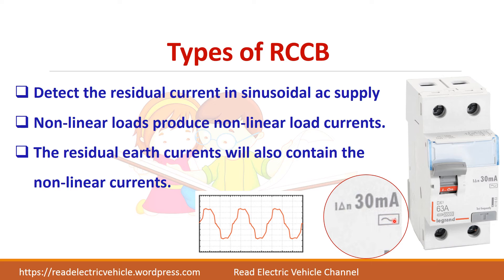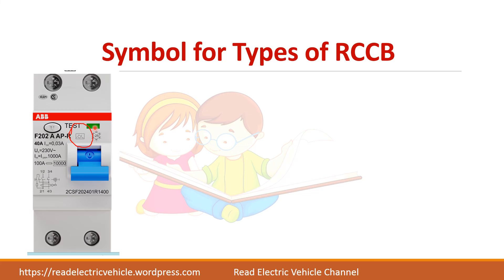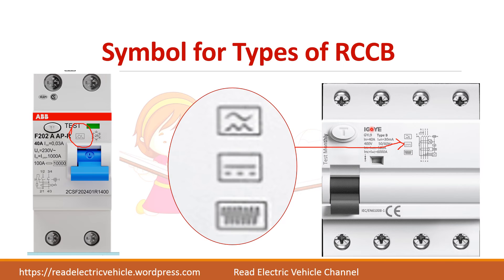The symbol on the RCCB shows what type of current it can detect. One model shows two waveforms: a sinusoidal one and a rectified DC waveform. Another model shows different waveforms — sinusoidal, a DC waveform, a smoothed DC waveform, and a high frequency signal. These are the types of waveforms that can be detected by that particular RCCB, and it will be specified by the manufacturer.